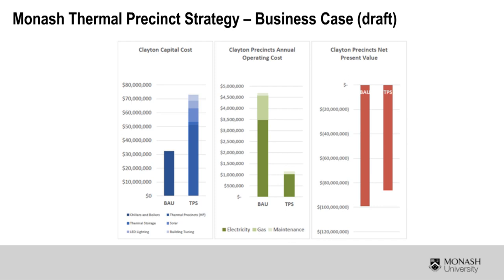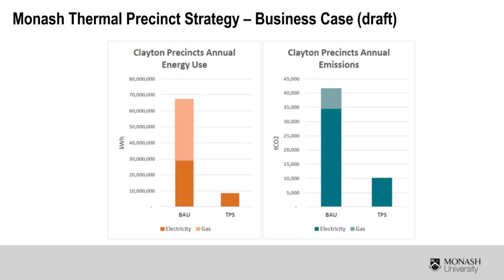From an operating cost and maintenance perspective, that's essentially where the key savings are compared to business as usual. We eliminate our gas costs and significantly reduce electricity costs, particularly because it's more efficient, using about a third of the energy, plus savings on peak demand charges. So the one in red, when we look at the net present value over the 20-year period, it was about a $9 million saving.